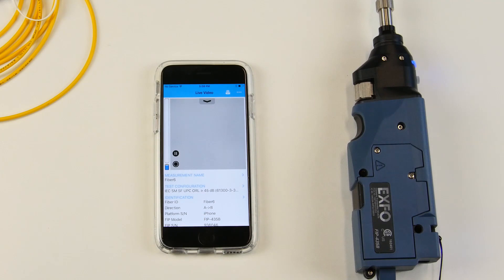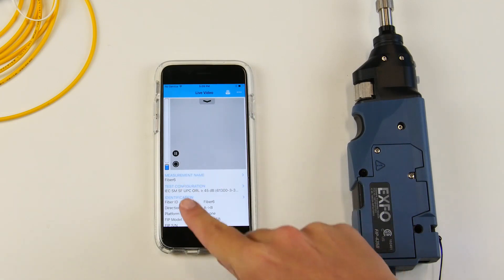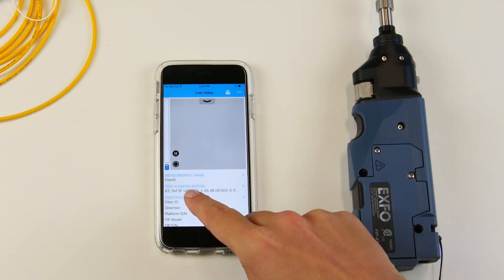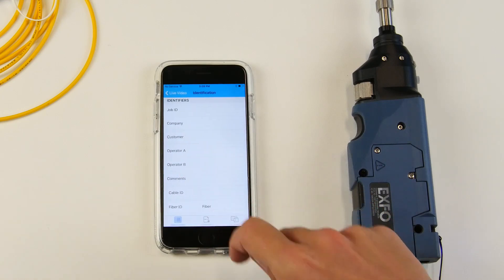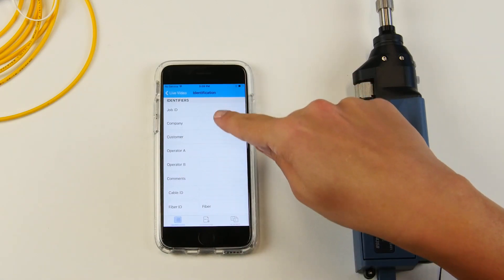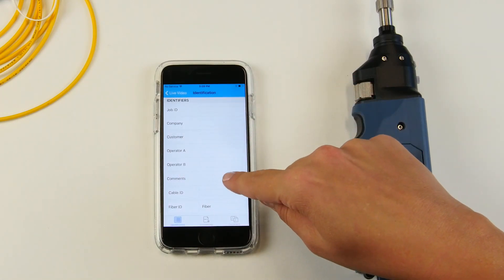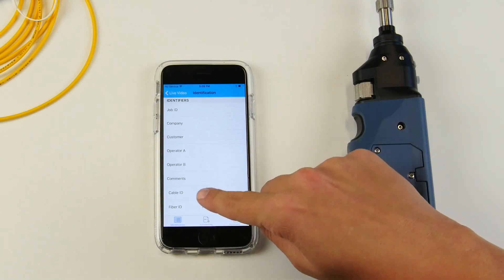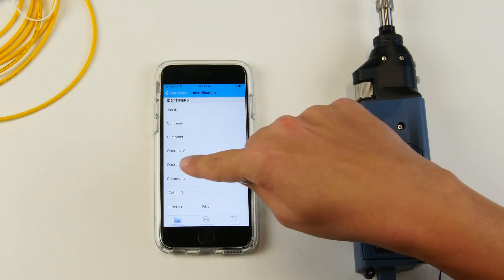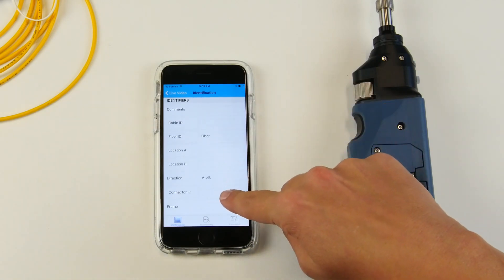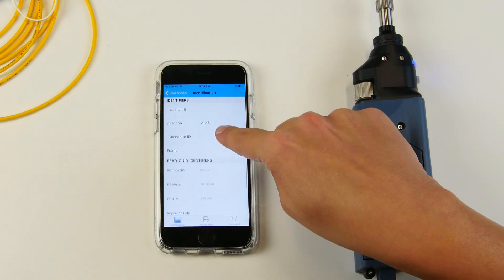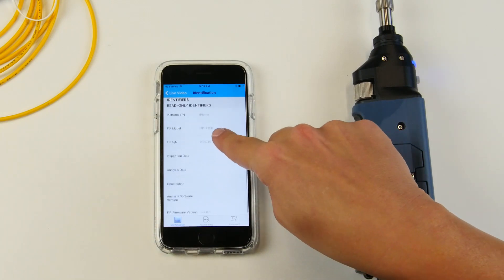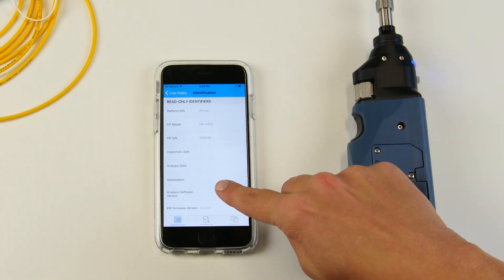Before you get started with the series of tests that you have to complete, you can actually configure the application using the different menus here. So you can press on identification where you can input all of the information that you need on your report at the end of the job. Job ID, company, location, direction, connector ID, and all of this type of information can be input here.